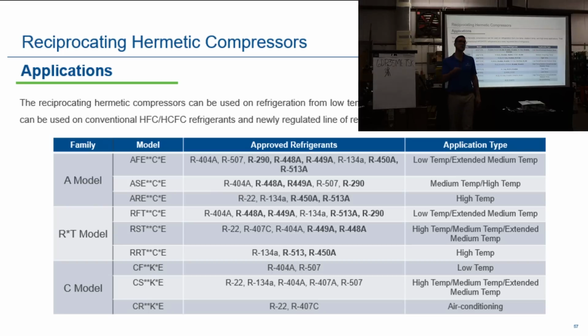You want to make sure if you're using low temp, you have the low temp compressor. You got to look in those AE bulletins that I talked about for that compressor to see if it's the right application. Because I've seen it many times where people would buy a compressor, they would go install it, and if they install a high temp compressor in a low temp application, do you think that compressor is going to run? Well, it's going to run for a little bit, right? Any questions on that?